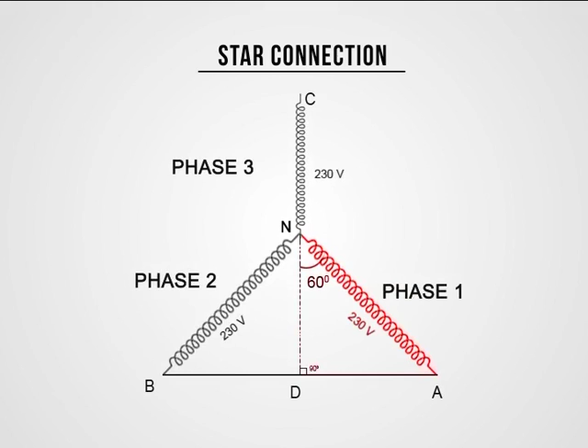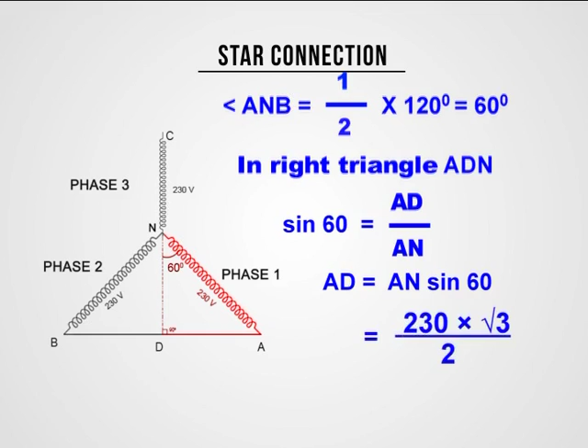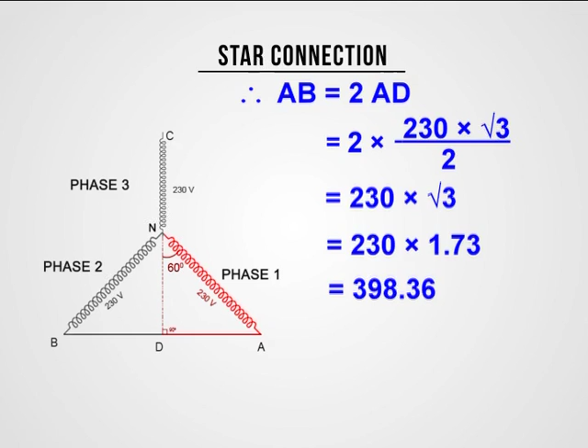In the figure, angle ANB equals half of 120 degree, equals 60 degree. The potential difference between any 2 phase lines equals AB. Consider right triangle ADN. Sin 60 equals AD divided by AN. AD equals AN sin 60 equals 230 root 3 by 2. AB equals 2AD equals 2 into 230 root 3 by 2, equals 230 root 3, equals 230 into 1.73, that is equal to 398.36, approximately equal to 400 volts.